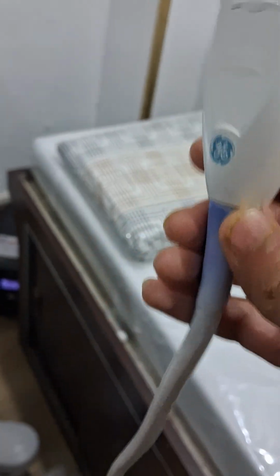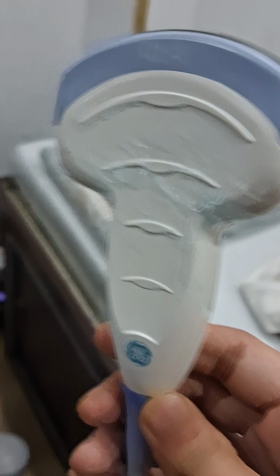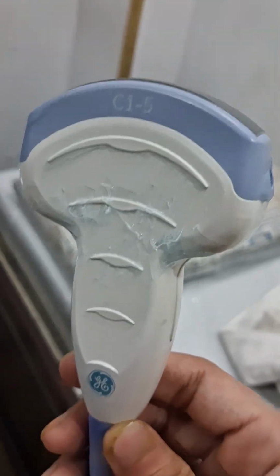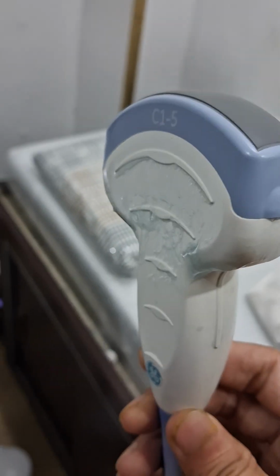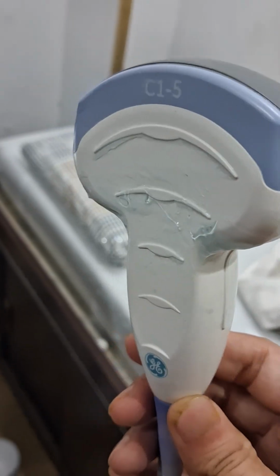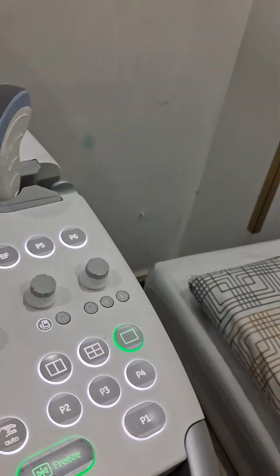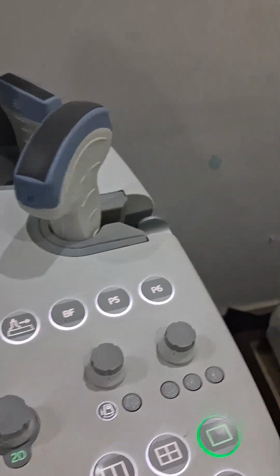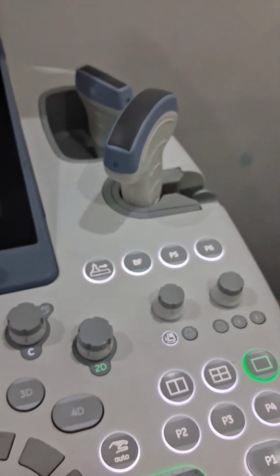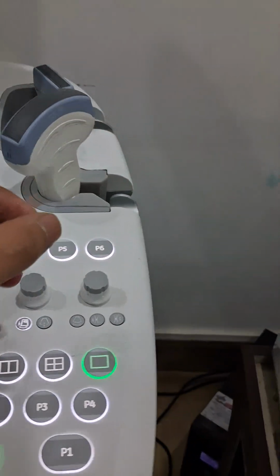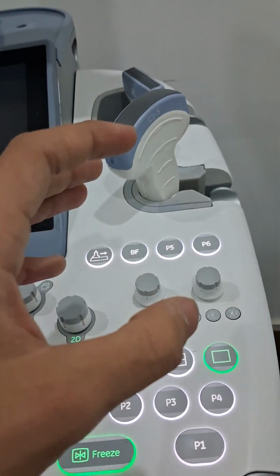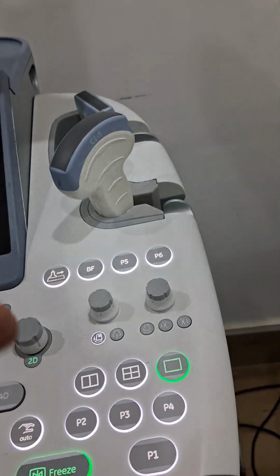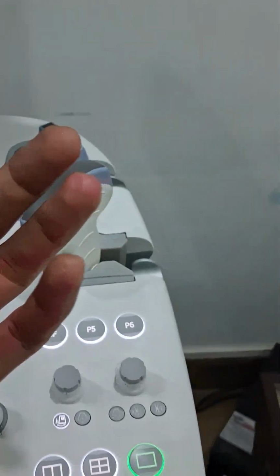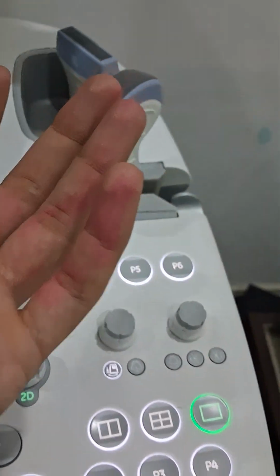So the electric current that is coming right from this wire into this probe is actually traveling through those piezoelectric crystals that are put inside this probe, and the sole purpose of those piezoelectric crystals is to generate the ultrasound waves. Okay guys, so what happened here? Here the energy is transformed from one form to another, because this probe received energy in the form of electrical signals, and it transformed those electrical signals into ultrasound waves. Ultrasound waves are also a kind of energy, we know that.